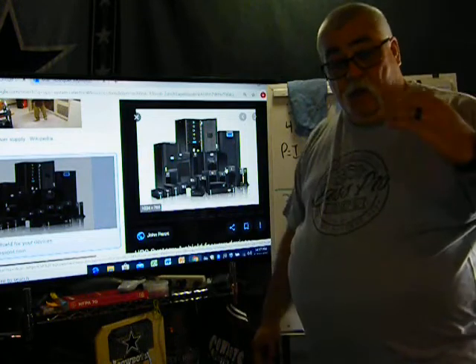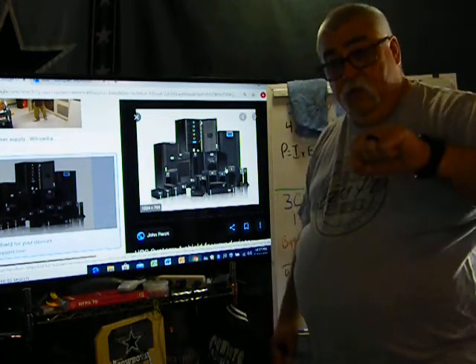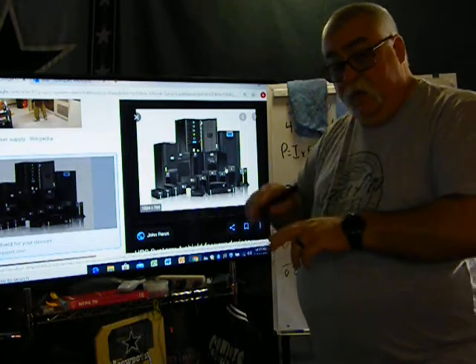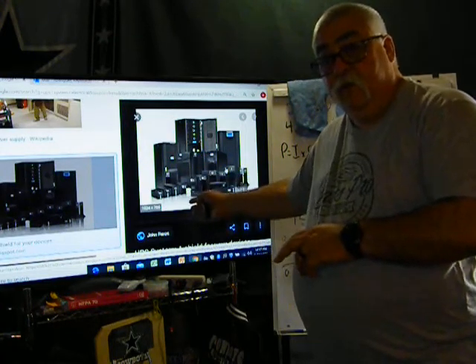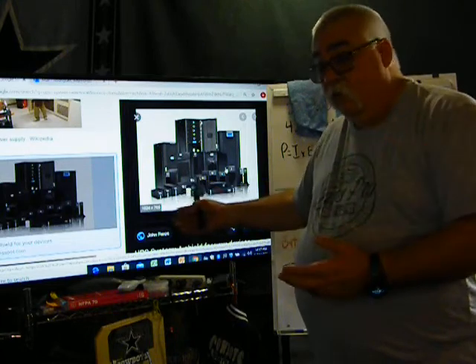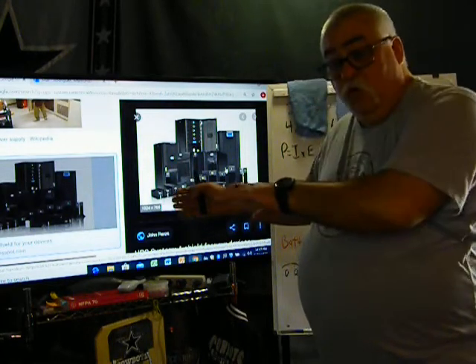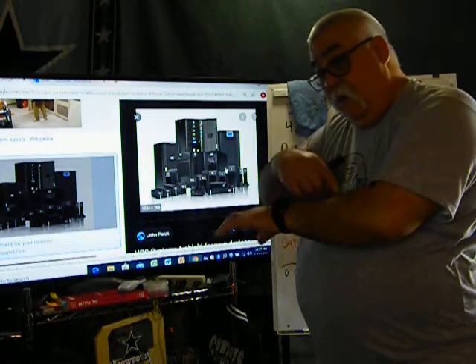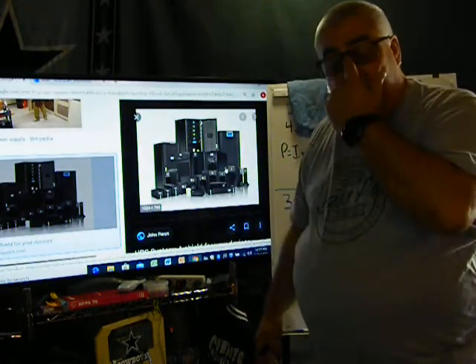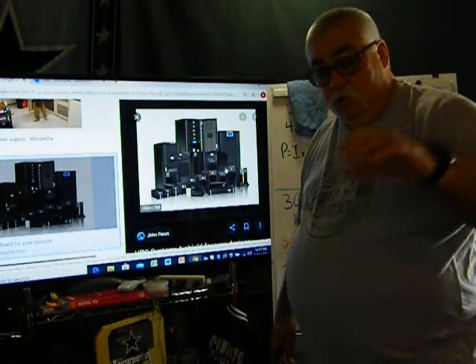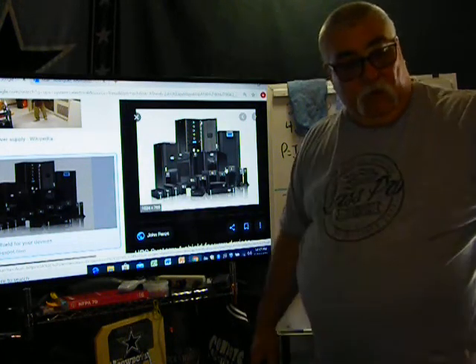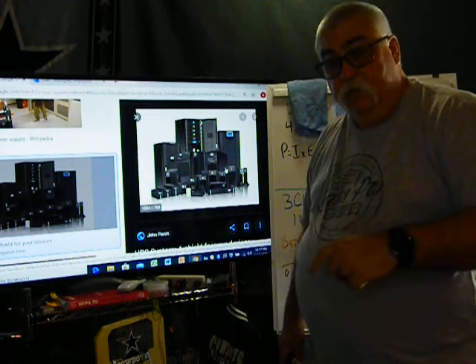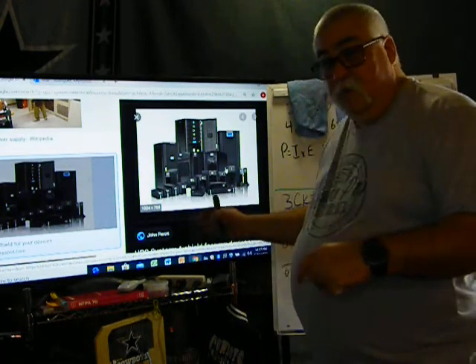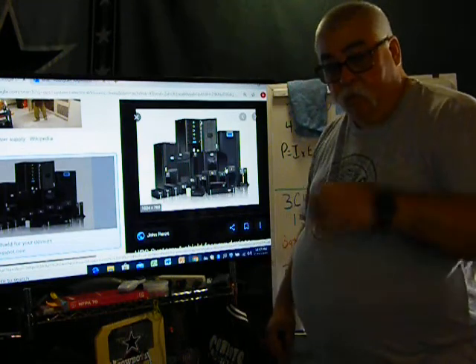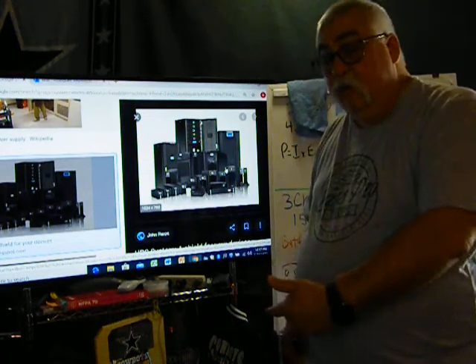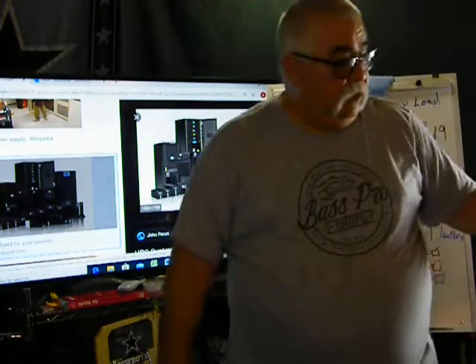Why? Because it's coming in off your electricity, going to a charger, charging the battery, coming out of the battery, going through an inverter, and changing it back to 120 volts or 240 volts, whatever your voltage is. Okay, but it's all going through the batteries. Unless the batteries go bad, and then you're screwed. So all it's doing is taking your power coming in off the utility and charging the batteries. The other side, the output, comes off the batteries. So there's no interrupted power. Guess what? It's only the batteries that aren't getting charged. Okay, same thing with these.